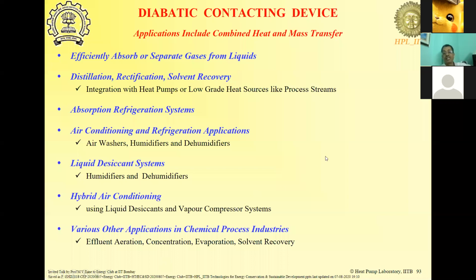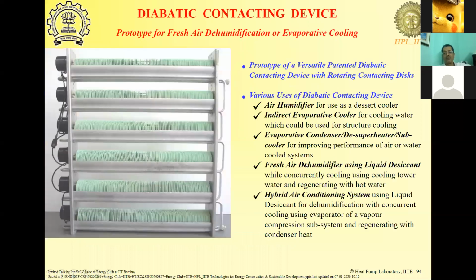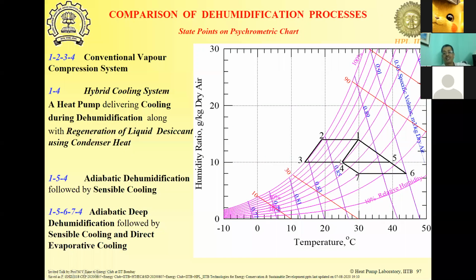In conventional air conditioning, we typically cool the air to dew point, cool it further to remove moisture, and then introduce it into the room. Either preheat it or just release it into the room. It mixes and then comes back to this. Now in this liquid desiccant based hybrid air conditioning, we can go from 1 to 4 in a single step. In a solid desiccant based, you go here and then you can come here, or you can do deep dehumidification and then ambient heat rejection and evaporative cooling to come here.